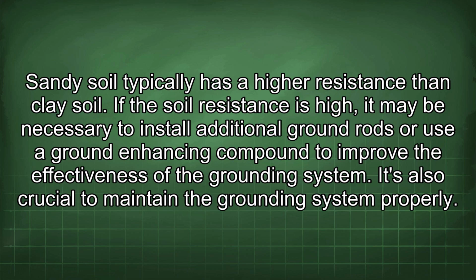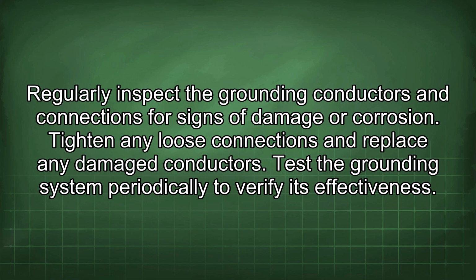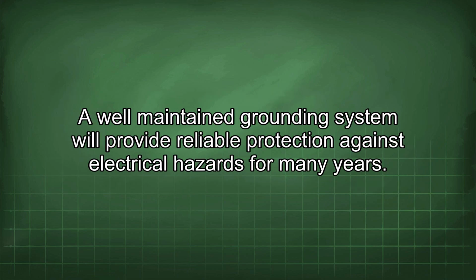It's also crucial to maintain the grounding system properly. Regularly inspect the grounding conductors and connections for signs of damage or corrosion. Tighten any loose connections and replace any damaged conductors. Test the grounding system periodically to verify its effectiveness. A well-maintained grounding system will provide reliable protection against electrical hazards for many years.